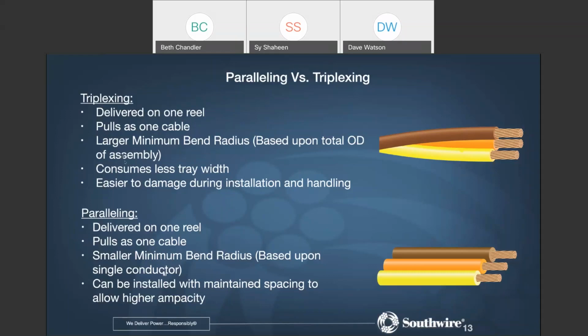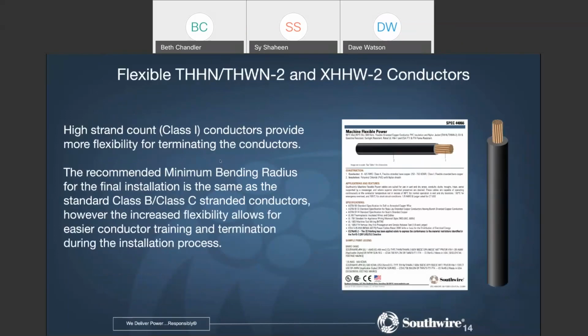It will consume less tray width because now the conductors are plexed and up higher, taking up more space vertically in the cable tray. Now, this is going to be a lot harder to handle and work with. Unfortunately, it's going to be easier to damage this because of the stiffness of the copper conductors, and especially once you plex it together, it does make it very difficult to work with. So it's going to be easier to damage during the installation and handling of this product as compared to paralleling or pulling individuals.